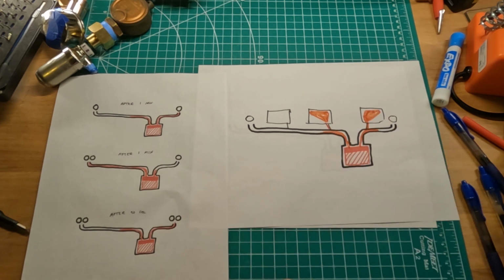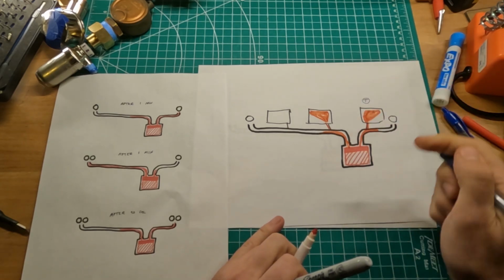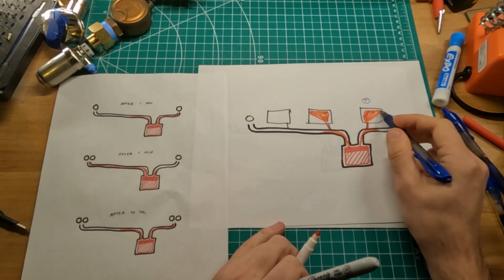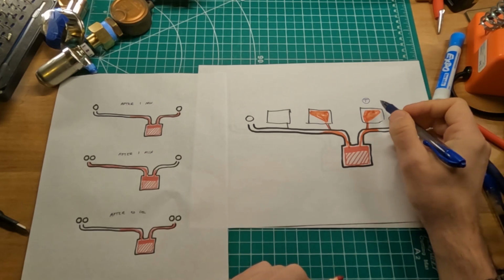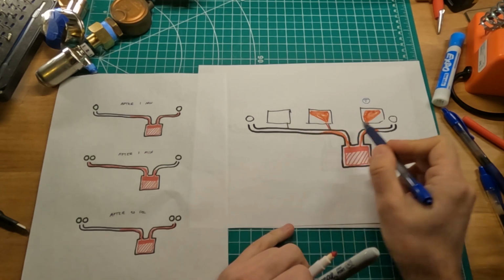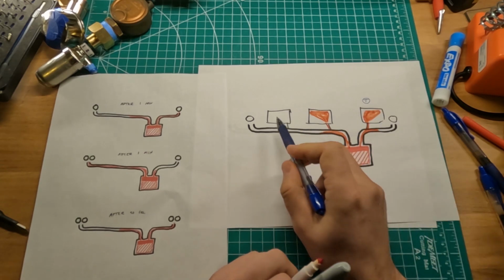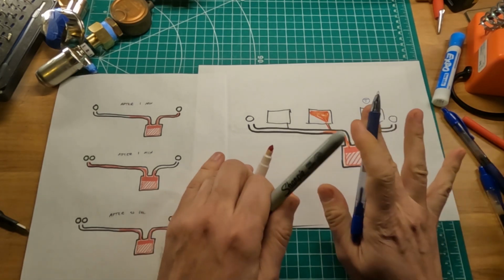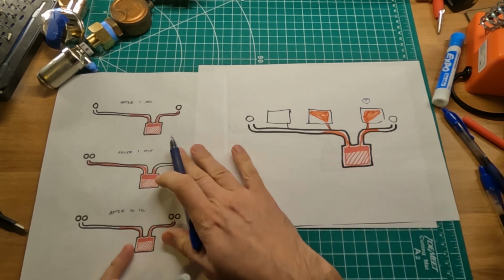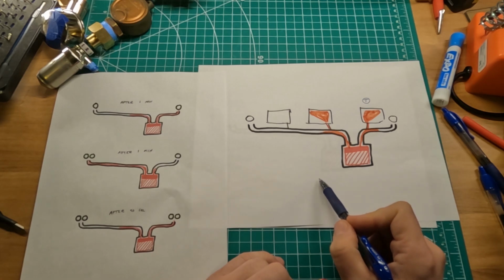Now what happens, let's say, if we have a thermostat set somewhere here? Because of that, this thermostat starts feeling the heat from this radiator, and then all of a sudden ends the call for heat from the boiler. So the radiator heats up, no more heat is needed because the thermostat is satisfied. So what happens with this radiator? And again, remember, this is by definition a slightly exaggerated drawing to get the basic principles of operation. Then this radiator stays cool or close to cool.